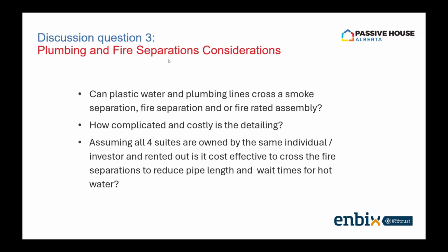So yeah, he's 100% right, you can't do it. I'll say that ULC has now come out with some really nice fire stopping that can go quite large, but when you're looking at residential, it ends up being really heavy duct, so guys that aren't familiar with commercial have a hard time really installing that stuff. You'd also need individual ventilation within your suites anyways—it's no different than a secondary suite where you have your own control. Because if you're pumping air into everyone's suite and bringing air back, if I burn toast in mine, you shouldn't be able to smell it in yours. So you have to have your own ventilation system per suite, unless you're treating it like a commercial building.